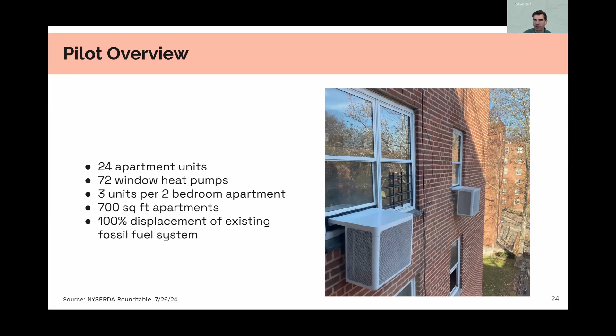They saved 85 to 88% of the heating energy. That's massive. That is what we frankly expected based on the roughly 60 to 80% efficiency of the boiler, and on the roughly 20% savings we estimated from not overheating the building.